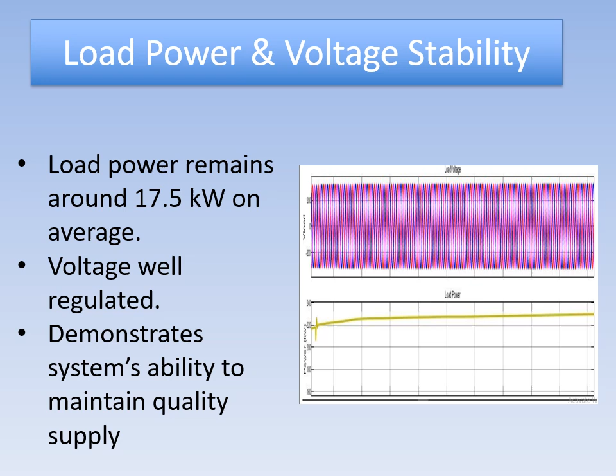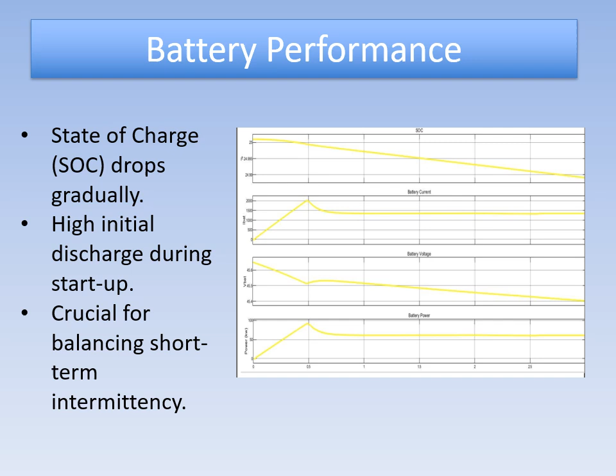Here we look at battery behavior through its state of charge, or SOC. At the start of simulation, we see a high initial discharge, which is expected as the system begins powering the load. Over time, the SOC gradually decreases depending on how much renewable energy is available to recharge the batteries. This shows how crucial batteries are in balancing short-term fluctuations when wind or solar production suddenly drops, like when a cloud passes. The batteries step in immediately to smooth out the gap before the diesel generator kicks in.